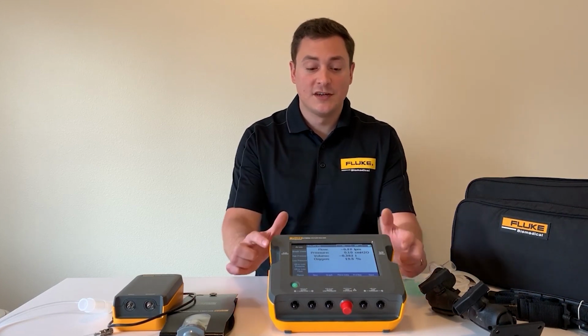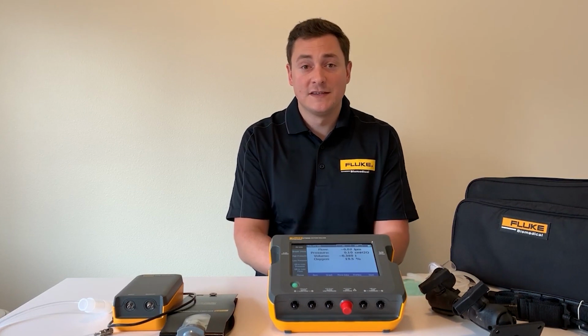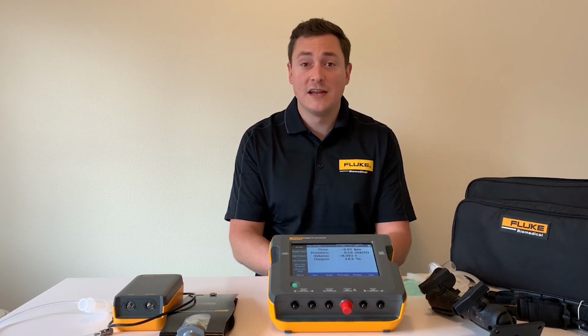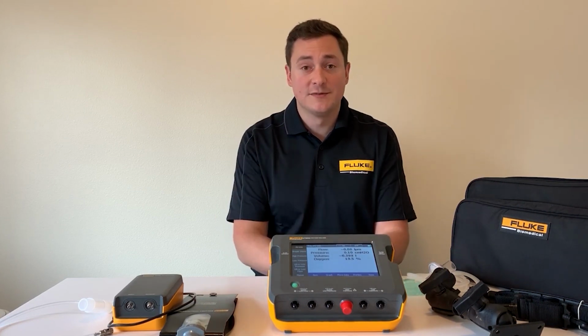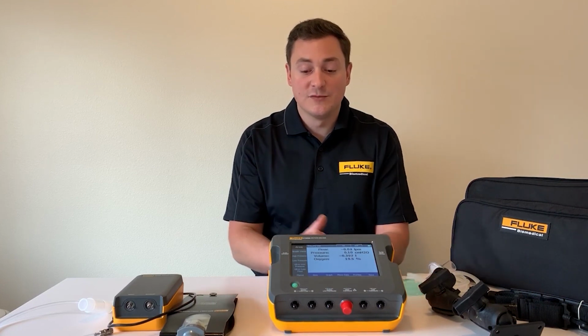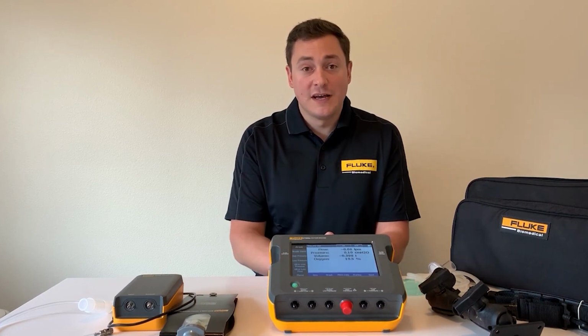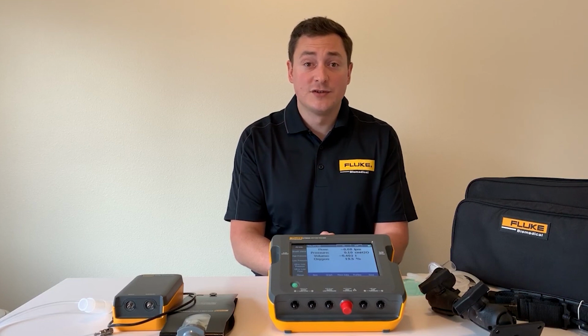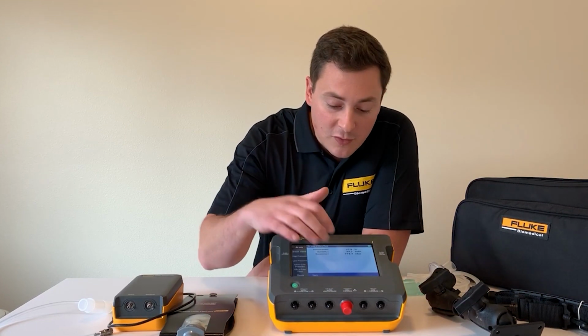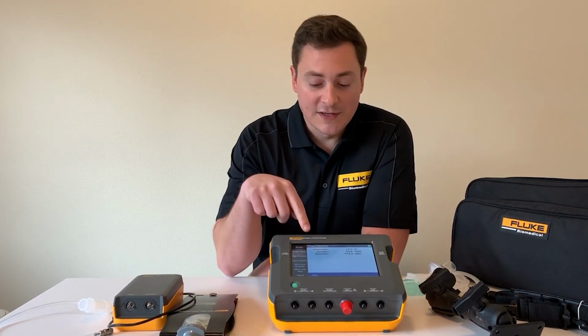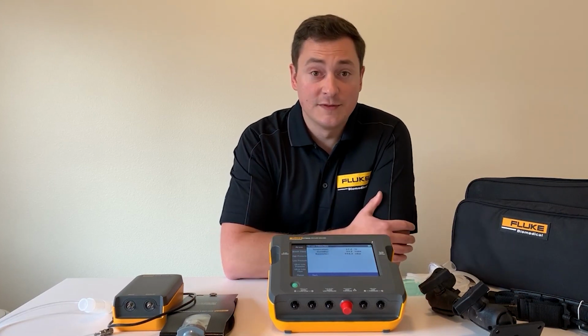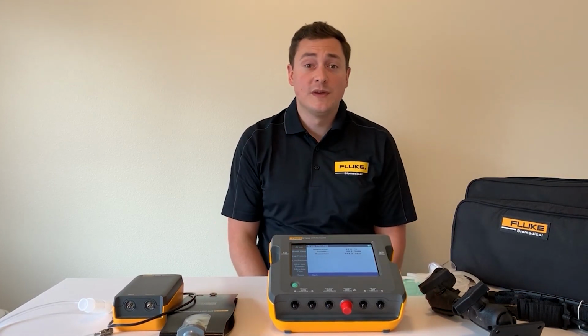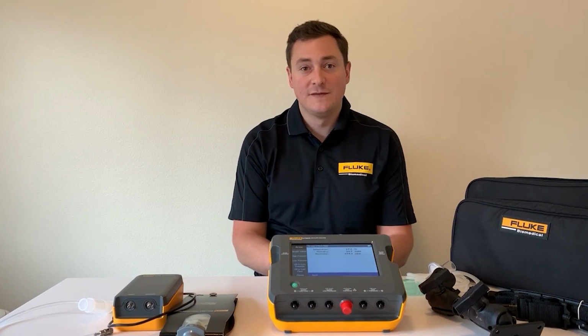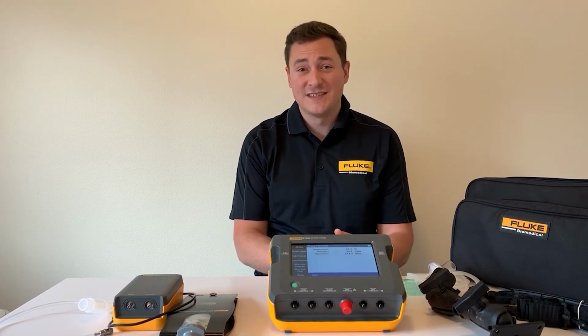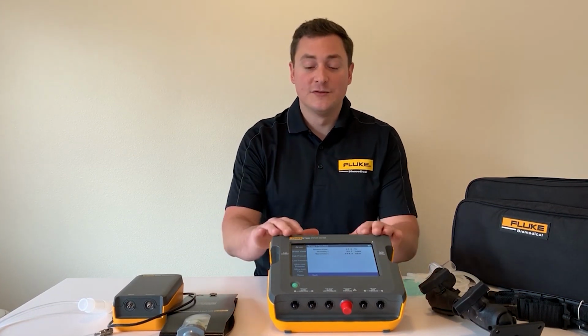The first thing I want to touch on is that we have a single flow channel. It does high and low flow, so you don't need to carry any modules and you don't need to switch test setups. So this is a really big game changer here. The other thing to point out is that it automatically compensates for temperature, pressure, and humidity. So if we go to more data, you can see that we take a temperature, humidity, and barometer measurement. So if you're taking extra test equipment with you to make those measurements, you don't have to anymore. If you're doing math on the side to compensate, you don't have to anymore. This will do it for you.